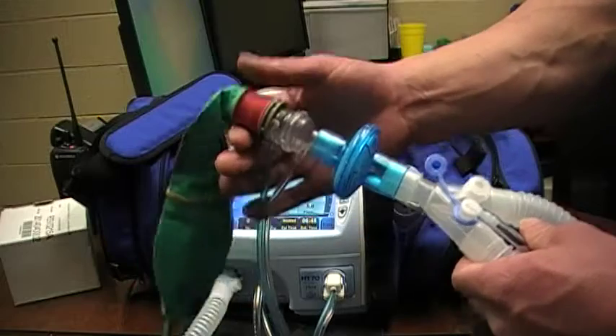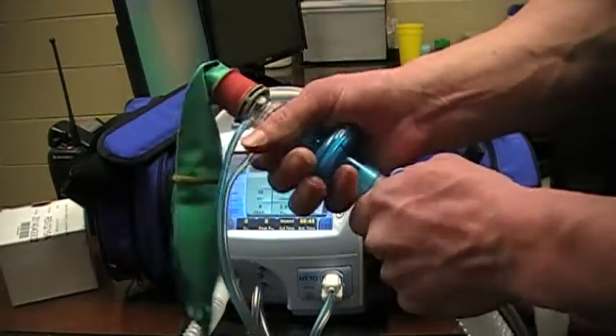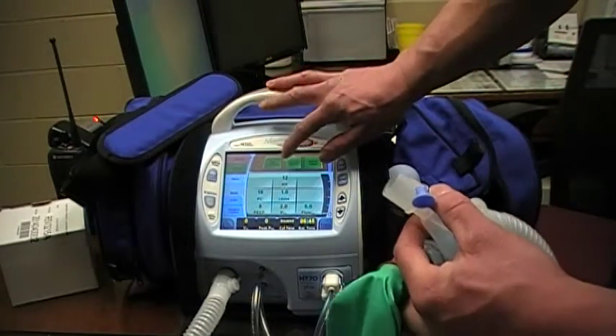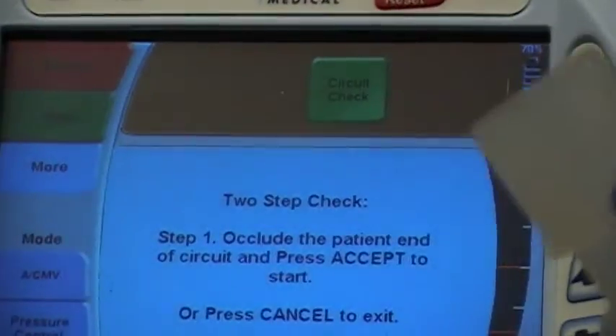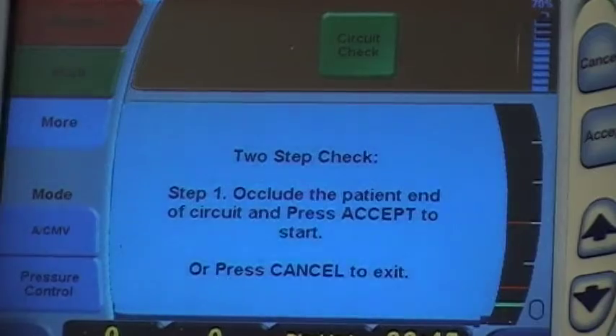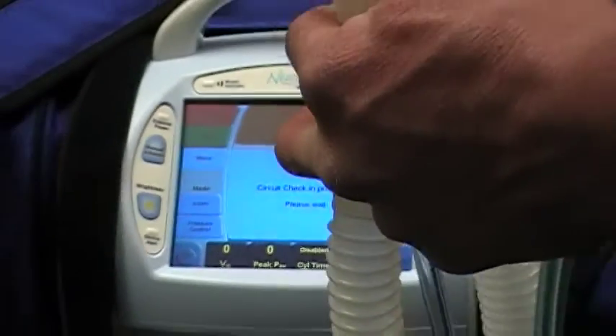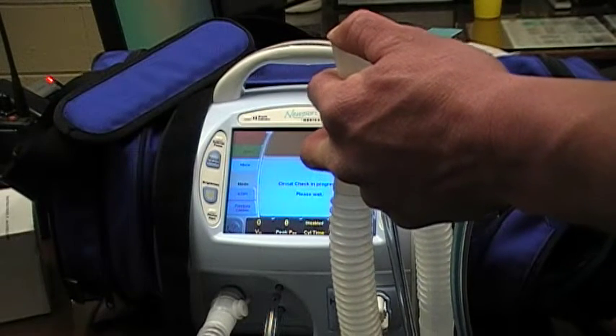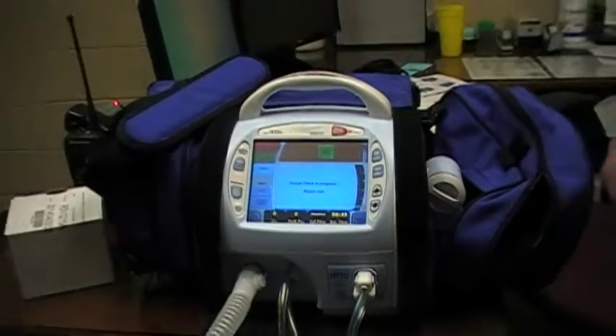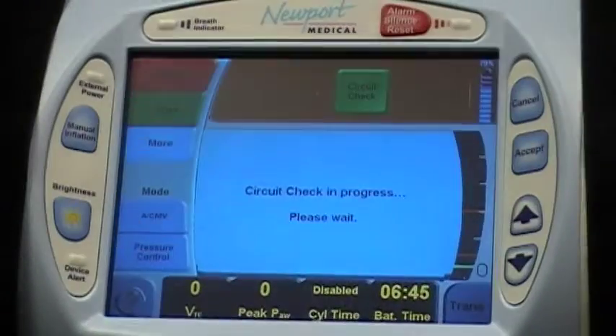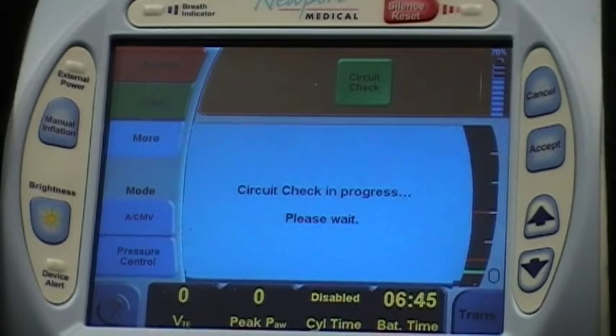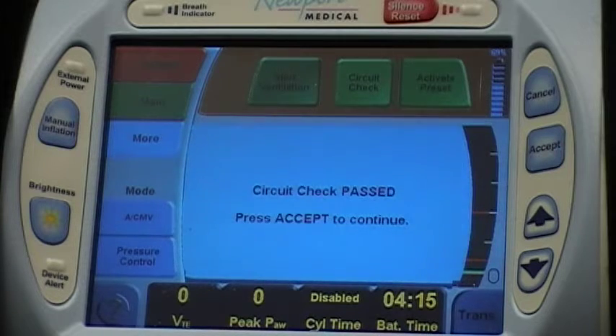Alright, so before I decide to ventilate the patient, I'm going to do a quick circuit check. To do that, I hit check circuit. Here it says occlude the patient end of the circuit and press accept. So I'm going to put my thumb over the circuit and hit accept. It says open the patient circuit and push accept, and then it will cycle and check the circuit for any leaks. Okay, so circuit check passed.